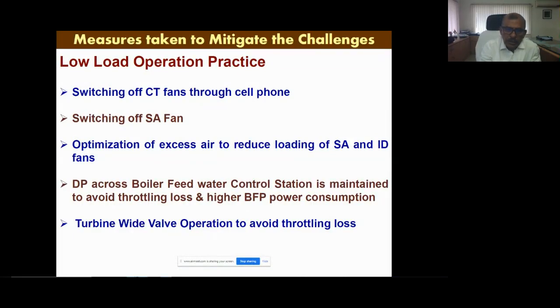Measures taken to mitigate the challenges of low load operations: earlier we used to run all the equipment. Now during low load operation, we switch off cooling tower fans through mobile cell phones. We switch off 1 SA fan, that is, shut it down during backing down or low load operation. Optimization of excess air to reduce the fan loading and reduce the auxiliary consumption. Controlling the DP across the boiler feed pump at low load operations, so that there will be no throttling, and we control it through the full fluid coupling control.